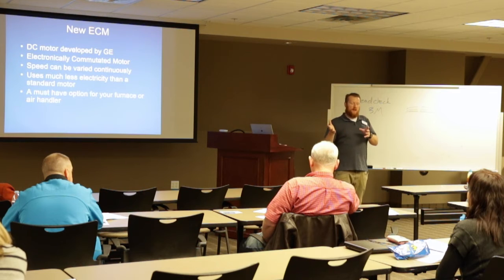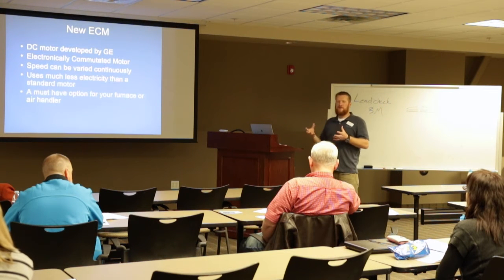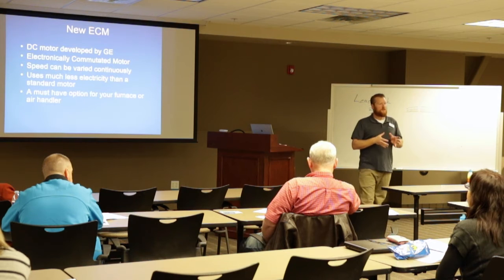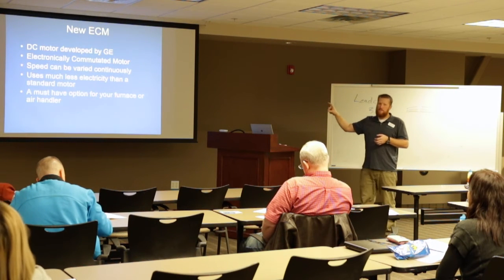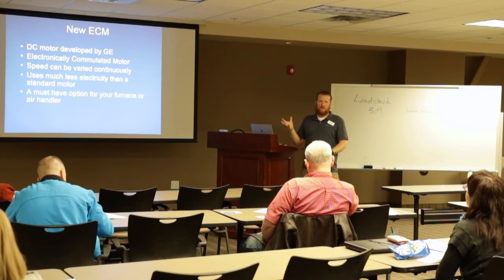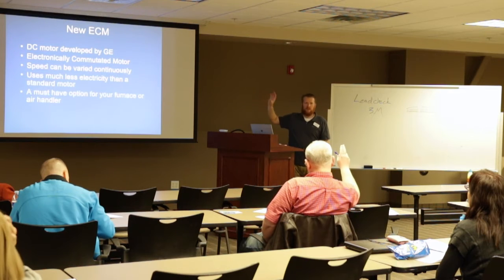But we started doing the math, and your average furnace with today's electricity rates, your average standard blower motor will run you about $700 a year to run it 24/7. An ECM motor will run you about $75 a year. So that's a huge savings in cost. An ECM motor, we had ours replaced a while back, and I think it was like $350. So you just paid for it the first 6 months of using it, if that's how you're going to use this continuously. So, new technology, huge efficiencies.